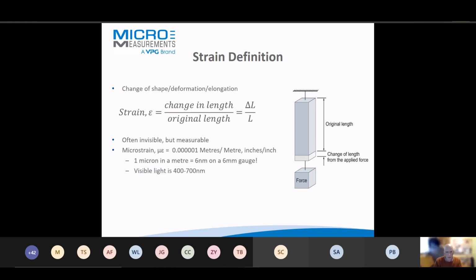That only becomes apparent how small it is when you consider the wavelength of visible light is between 400 and 700 nanometers. So we're essentially measuring things two orders of magnitude shorter than we could see in any visual system. If you think of this 6 nanometers on a 6 mm gauge, on a 1 millimeter gauge we're measuring 1 nanometer changes.